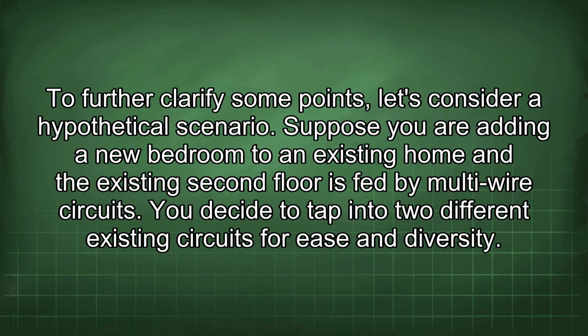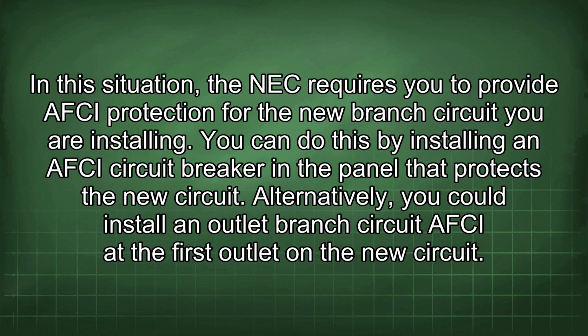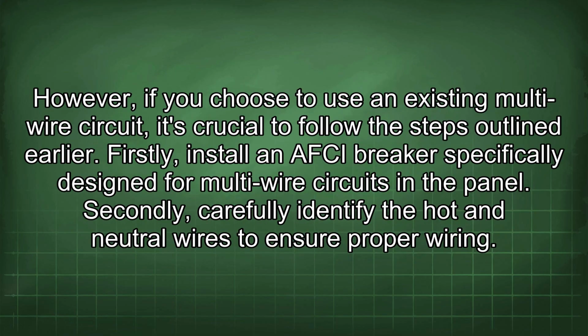To further clarify some points, let's consider a hypothetical scenario. Suppose you are adding a new bedroom to an existing home and the existing second floor is fed by multi-wire circuits. You decide to tap into two different existing circuits for ease and diversity. In this situation, the NEC requires you to provide AFCI protection for the new branch circuit you are installing. You can do this by installing an AFCI circuit breaker in the panel that protects the new circuit. Alternatively, you could install an outlet branch circuit AFCI at the first outlet on the new circuit. However, if you choose to use an existing multi-wire circuit, it's crucial to follow the steps outlined earlier.